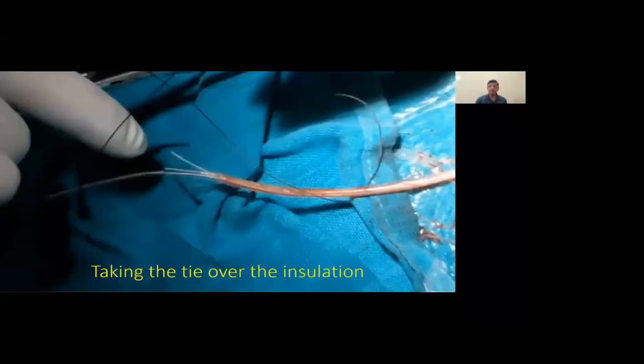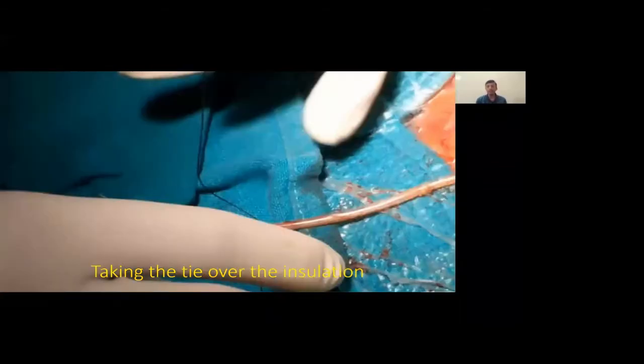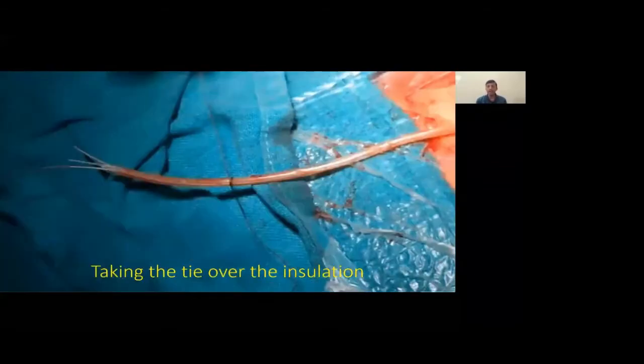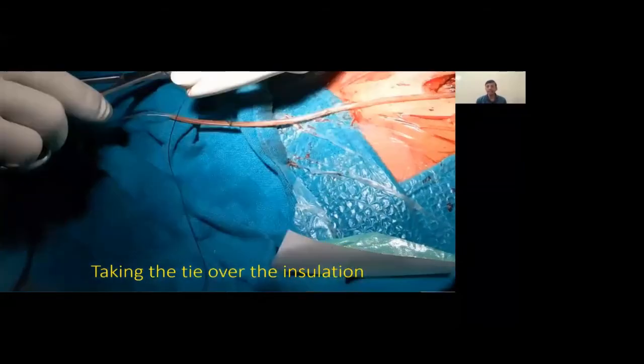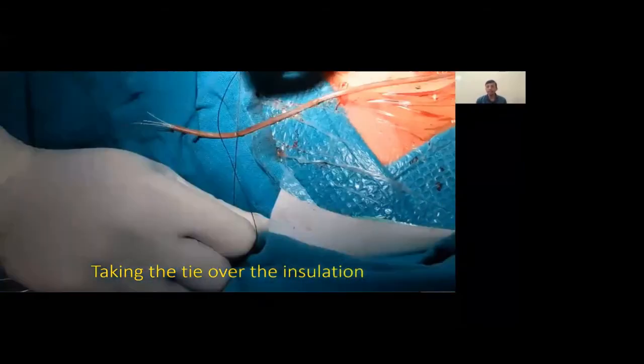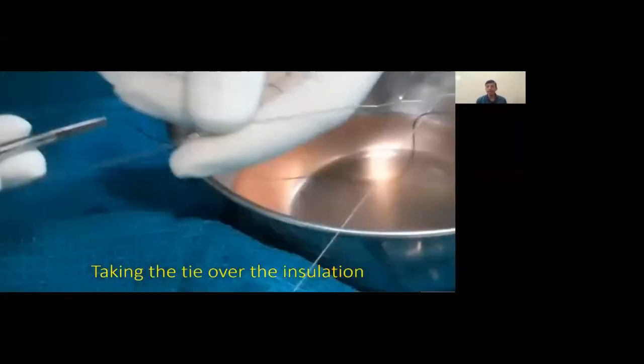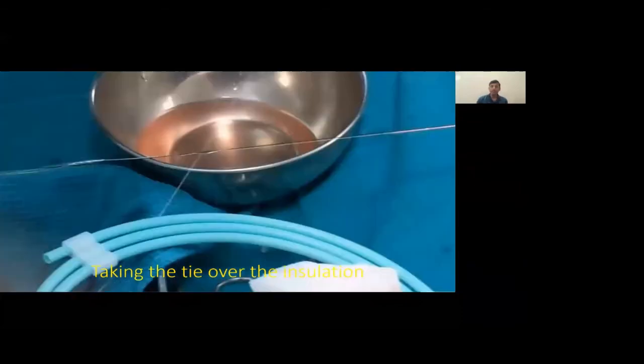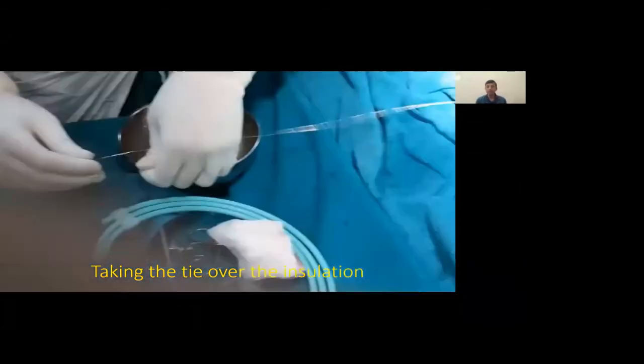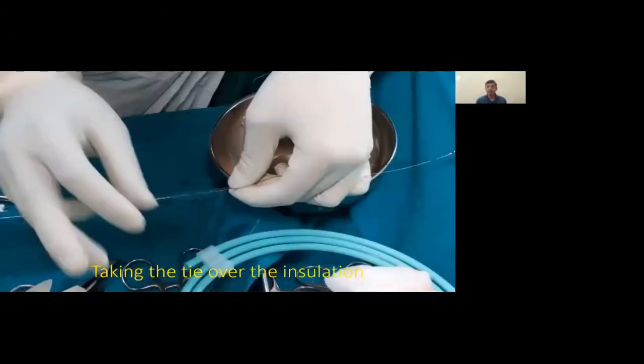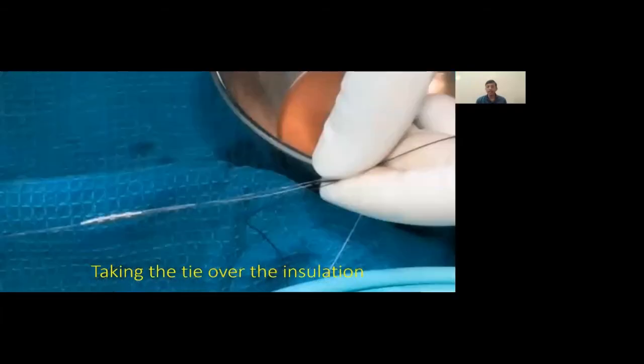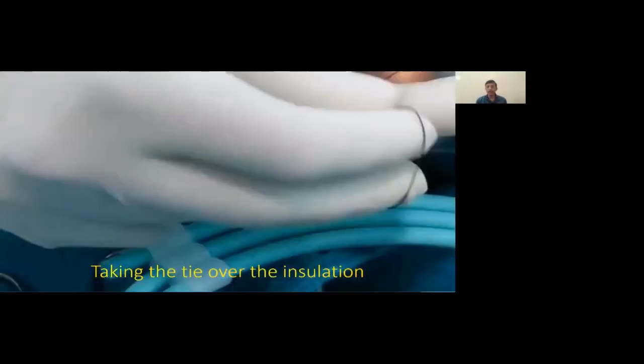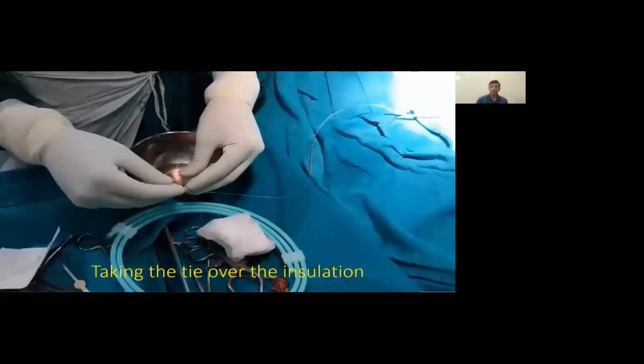Once the lead locking device has been deployed, one needs to take ties over the insulation. It's good to take 2 or 3 ties over the insulation so that the entire lead and its insulation is one single unit and helps you when you give traction. So this is just a video that quickly shows you how you take the tie over the insulation and secure it to the other end of the lead locking device.